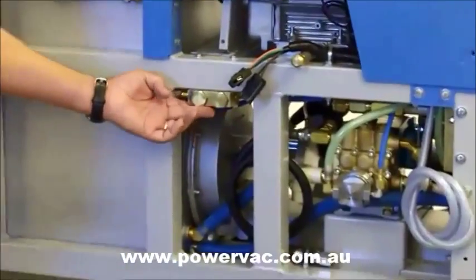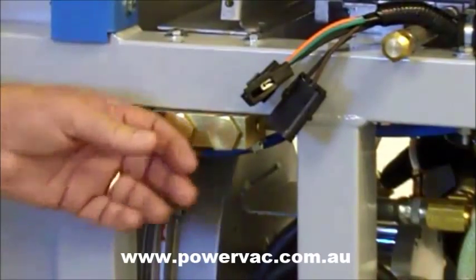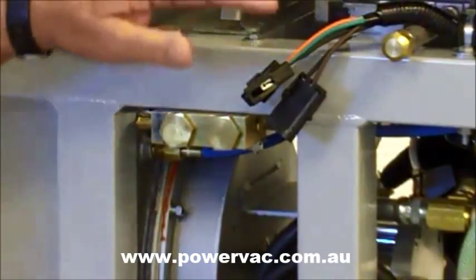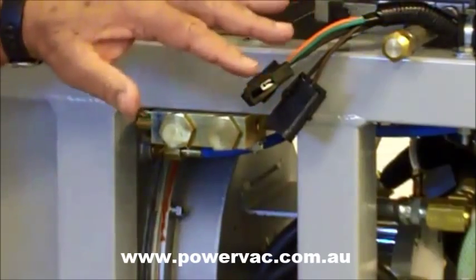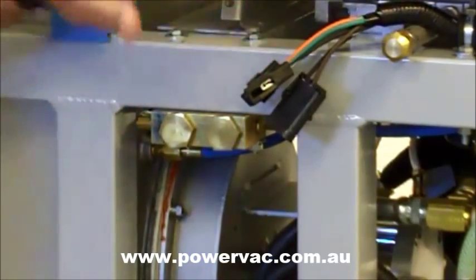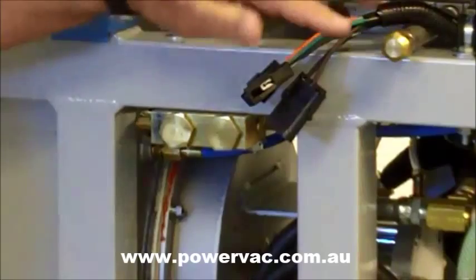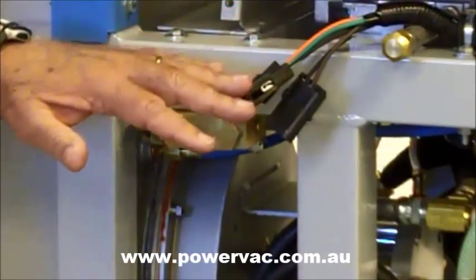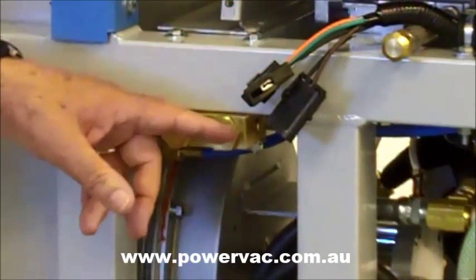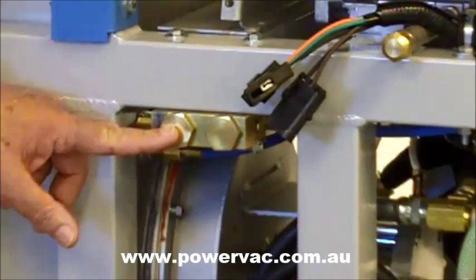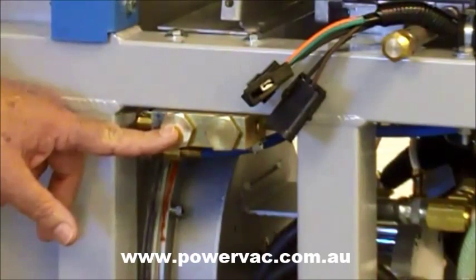Another maintenance point is the manifold for the bypass orifice. The bypass orifice keeps the water circulating through the machine to keep temperatures even and allows the sensors to know what's going on with the pressure system the whole time. There's two nuts on here. It takes a 15/16 wrench to take them off.